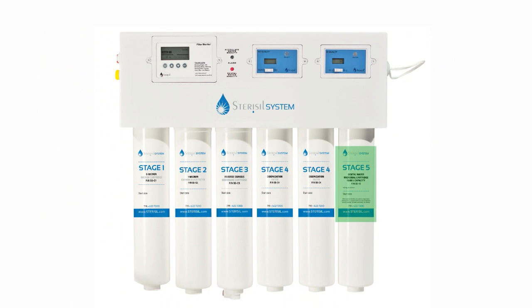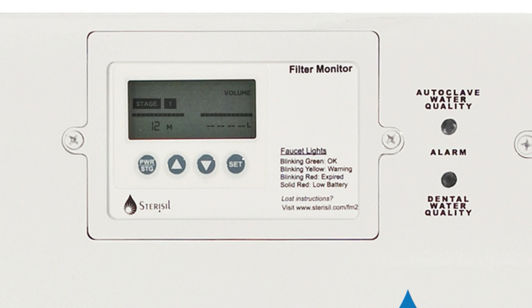Look at the label of your current Stage 5 cartridge to ensure you are ordering the correct part number. In order to ensure that the Sterisil system is properly monitoring your water usage, it is necessary to reset Stage 5 of the Filter Monitor each time a new Stage 5 cartridge is installed. It is suggested that you order a replacement cartridge when the system's dental water quality LED turns yellow, as your Stage 5 cartridge is beginning to exceed 90% of its US EPA registered capacity. This will allow time for your new Stage 5 to ship, so that it can be available to you immediately after your current Stage 5 is expired.